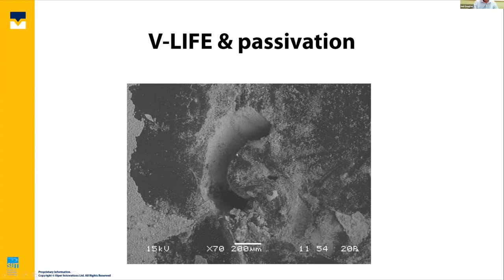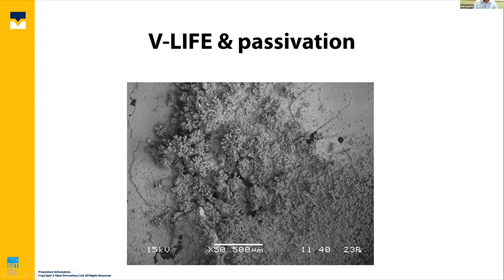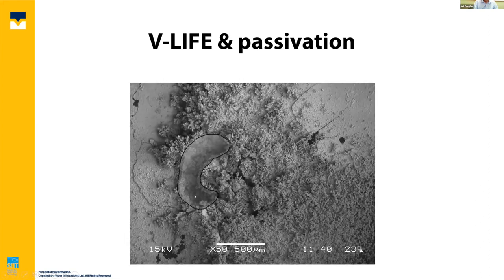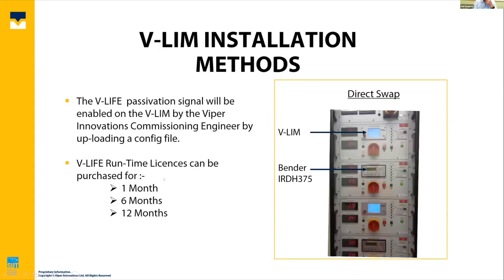It was made with a pair of tweezers, but it goes all the way down to the copper in the bottom. After we have applied V-Life, that same hole looks like that. So that's where the hole was. You can see what we've actually done is filled the hole with this precipitate, and that has pushed the water out and effectively increased the insulation resistance. And so now, because your insulation resistance is high, you don't have that copper loss or degradation of your copper conductor.